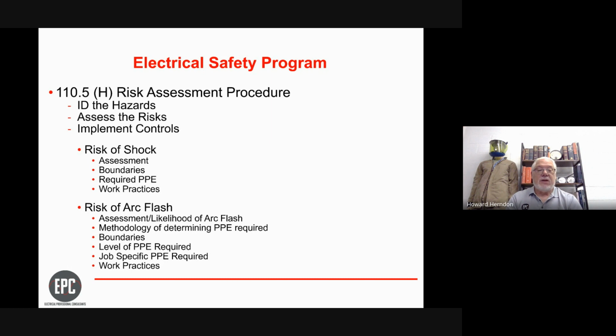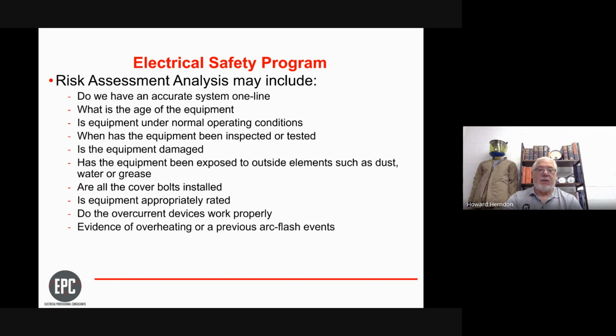The risk for arc flash involves very tough calculations typically done by computer. There are a couple of charts in the 70E book, but the problem is they have a lot of generalized requirements, and if we don't meet those requirements we can't use them — we have to go through the calculations. We have to create boundaries for qualified and unqualified people regarding PPE, and look at the level of PPE and work practices required. These are the areas of risk assessment for arc flash and shock that we need to examine.